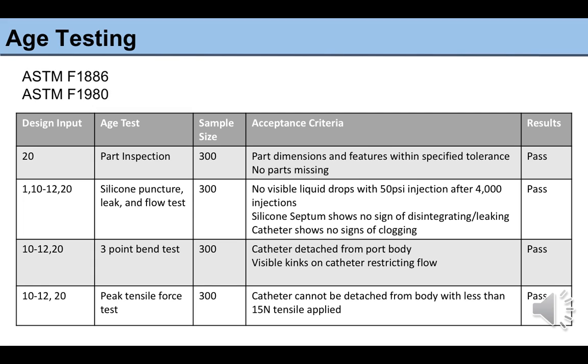Further, we completed a 3-point bend test to determine whether or not the catheter would detach from the port body, or if any visible kinks were arising on the catheter to restrict the flow. Finally, we did a peak tensile force test to determine whether or not the catheter could be detached from the body with less than 15 newtons of tensile force applied. All of these tests passed, and the sample sizes were all 300 because they were attribute tests.